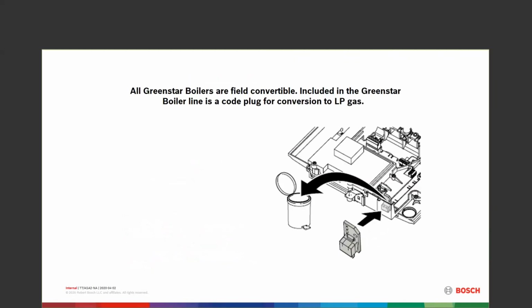The Greenstar boiler comes with a conversion kit, and in that conversion kit is a code plug. That code plug winds up in the upper top left corner if you're looking from the back of that control. On a floor boiler, you'd open the door, it'd be up in the upper left. On a wall boiler, it's actually going to be in the lower right. Same place on the control, but you're going to flip that control down on a wall boiler.